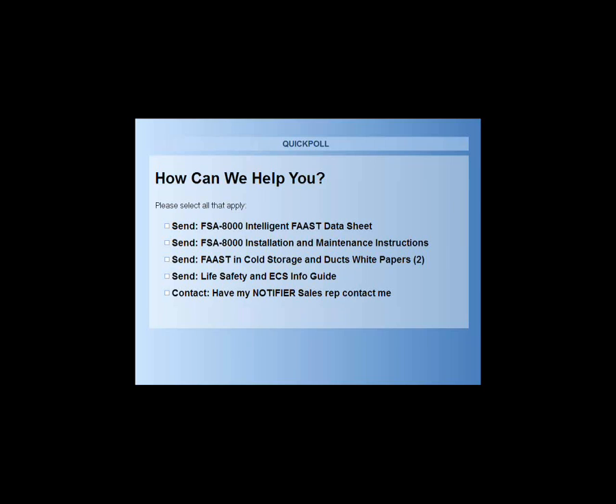Yeah. Okay. They're wondering about coverage area, both min and max, for the Intelligent FAAST unit. The maximum coverage area is going to be 8,000 square feet. That's in standard fire detection, so just normal sensitivity mode. That obviously goes down as you get into your very early warning type detection requirements. So your sample ports per code are going to have to be closer together, and your transport time when you get down to very early warning can only be a maximum of 60 seconds from the farthest sample point.